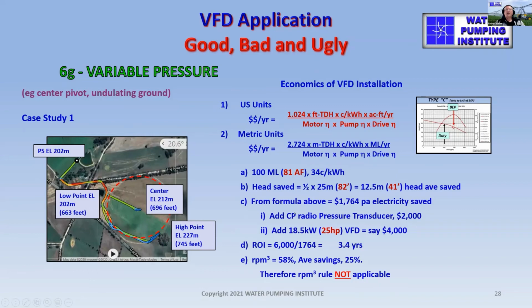If we add the cost, that's the OPEX. If we look at the CAPEX, what are we going to have to spend to achieve that? We need a pressure transducer, a kit to go on the end of the center pivot. That'll be about 2,000 fitted, and we need an 18.5, 25 horsepower VFD, say 4,000. So that's a total CAPEX of 6,000. Divide by the annual saving of 1,764. That gives you a return on investment of 3.4 years, and that's pretty good. That's really well worth adopting.